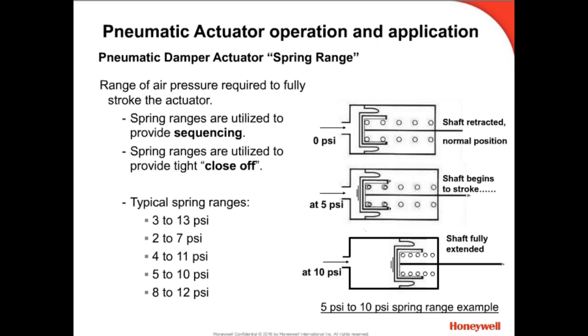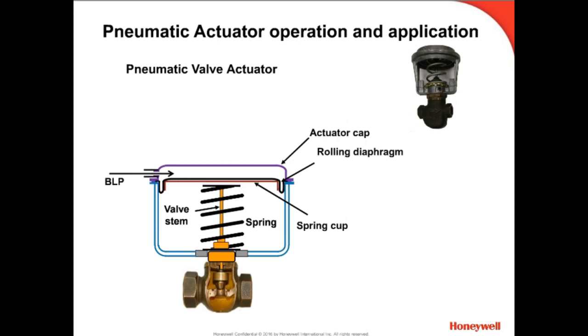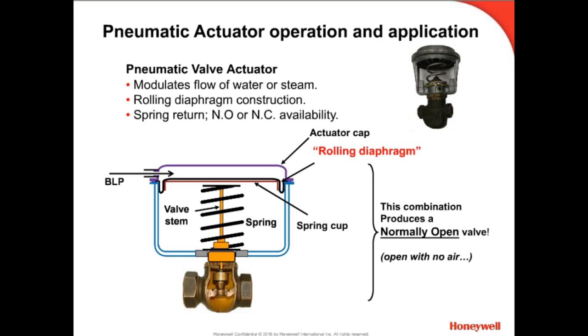The distance any shaft extends is the stroke specification, which will vary between actuator models. Pneumatic valve actuators consist of a diaphragm, push rod, and spring similar to a damper actuator. The rolling diaphragm design minimizes wear, providing a long, trouble-free actuator life. The spring-to-diaphragm relationship provides the normally open or normally closed configuration, and spring pressure ranges are available for sequential control of valves or to provide positive close-off force.